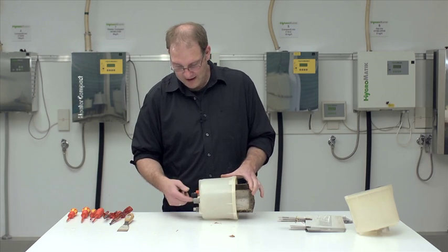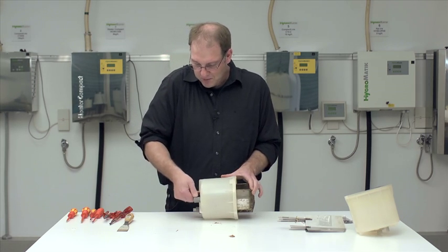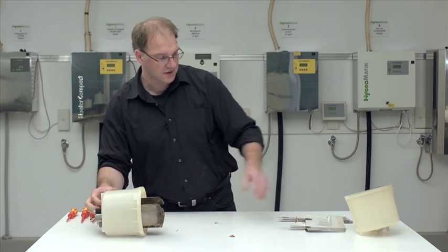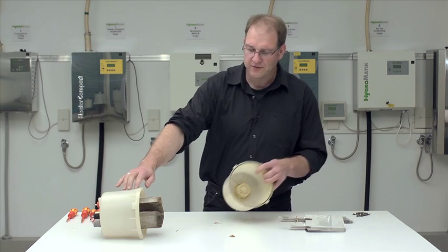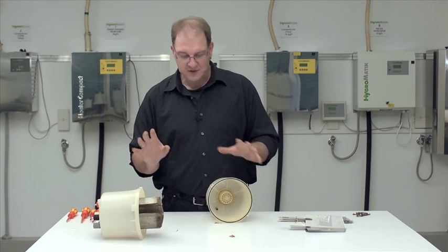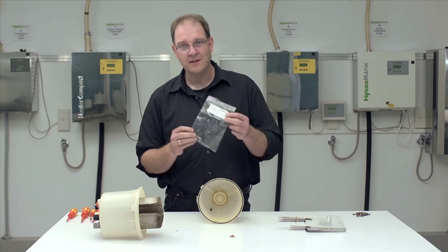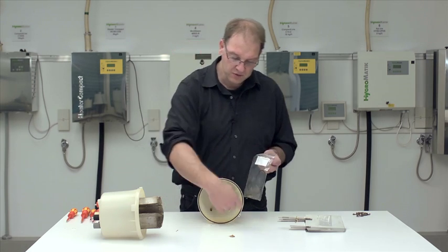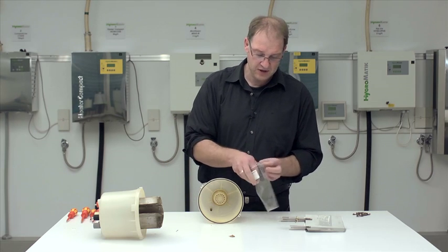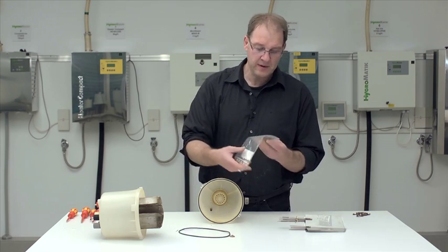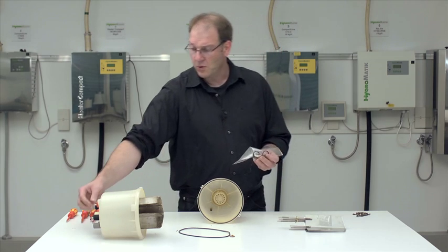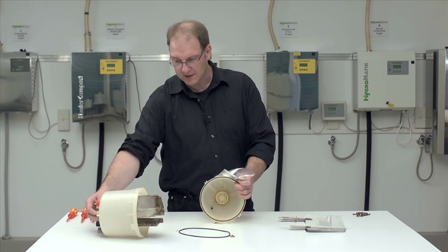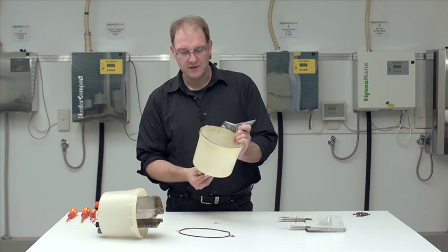Well, I have now fixed the last knurled nut here. Then I will just go on to the bottom part of the cylinder. And I would like you to strongly note, when you go about handling the steam cylinder, please always have an o-ring set at hand. In this o-ring set you will find one large o-ring for this cylinder flange, and this is the one I'm going to replace shortly, plus we have another o-ring for the top for the steam hose adapter, plus another one here for the lower part of the cylinder to connect that to the base.